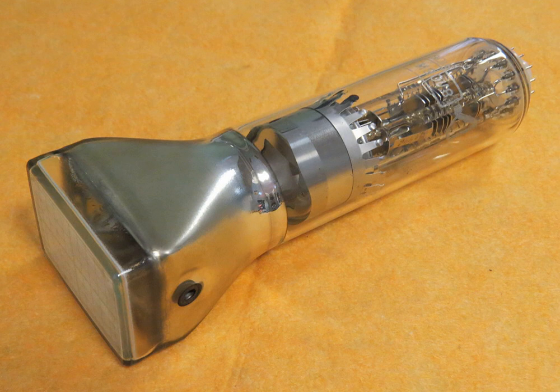on the CRT characteristics. An example of a practical application is if a pair of sine waves of known frequency are used to generate a circular Lissajous figure and a higher unknown frequency is applied to the Z input. This turns the continuous circle into a circle of dots. The number of dots multiplied by the XY frequency gives the Z frequency. This technique only works if the Z frequency is an integer ratio of the XY frequency, and only if it is not so large that the dots become so numerous that they are difficult to count.